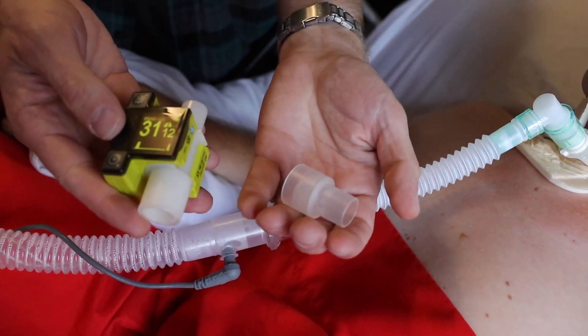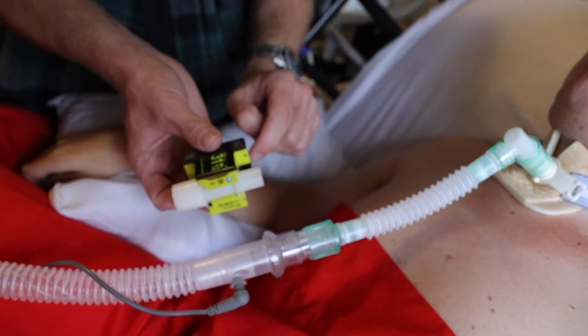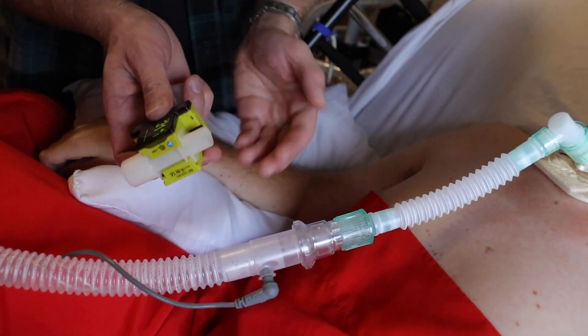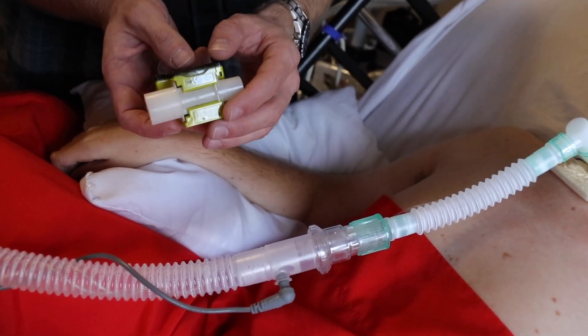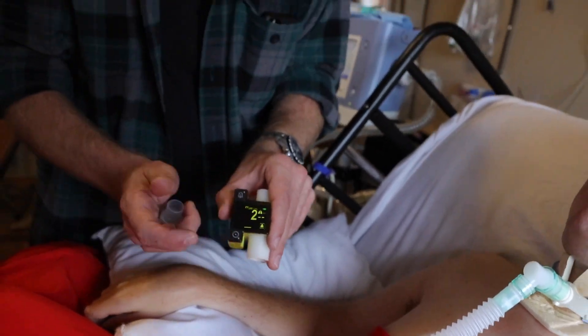You will need the Emma as well as the adapter, otherwise the unit doesn't fit — at least not here right above the whisper swivel. It does need to be above this because this is where the exhalation occurs, so you're not going to capture any exhaled CO2 if you put it below. But otherwise it works very nicely. Again, an impressive little device for something the size of a pulse ox. I like it quite a lot. Thanks for watching.